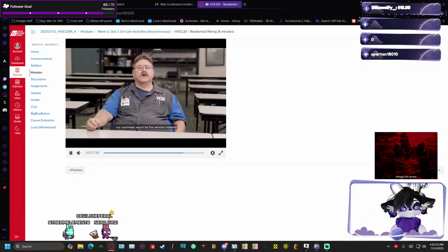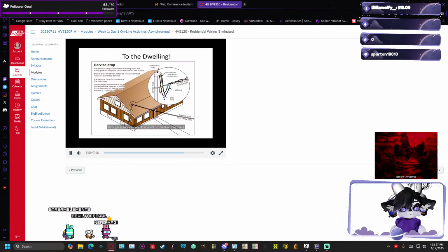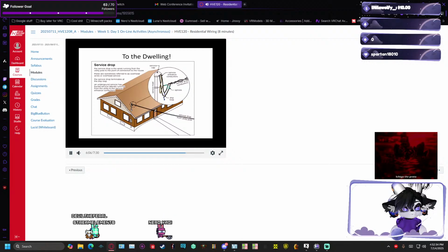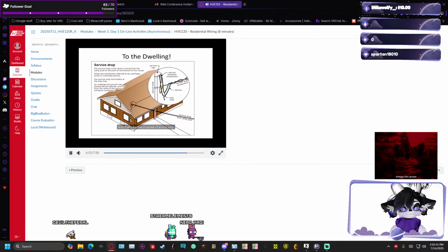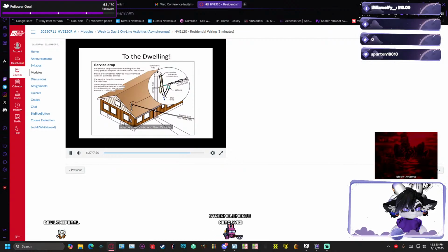To our overhead would be the service mast through a service cap, and you'll notice that they have 3 to 4 foot of wire required by the utility companies coming out of the service head for them to make their connections to it, and that's for the purpose of a drip loop. So any condensate, rain, or moisture on the wires won't go down into our electrical, and then the service head or our weather head also help prevent water from getting into where our connections are open and exposed. And it's called a service mast.